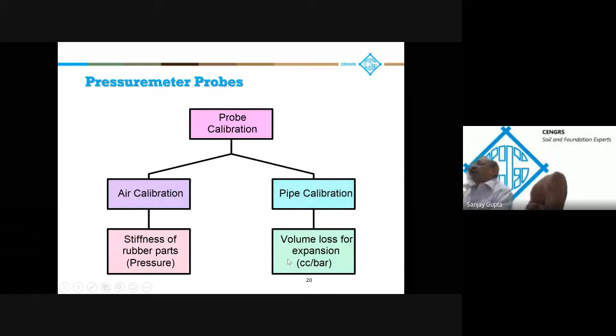Now let me quickly take you over to the flow diagram. We will see the three different things: the panel, the gas cylinder, and the probe. Now, how everything goes together. The pressuremeter test unit, as we talked, has a control panel. Control panel is basically to measure the water changes, the pressures. These pressures you have to measure for the guard cell, which is the gas, and the measuring cell, and the water cell is connected with the volume changes. All this is combined with the coaxial cable, which goes here. Now, this one is going to the radially expanded probe.